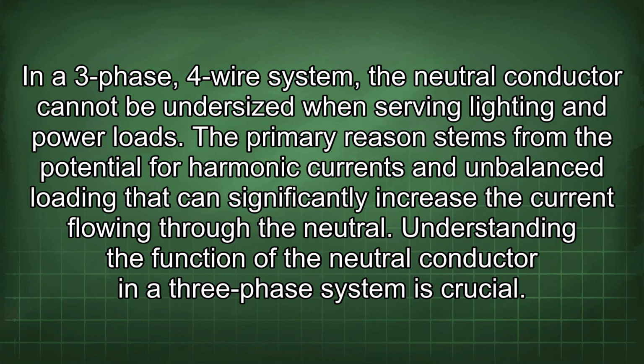In a three-phase, four-wire system, the neutral conductor cannot be undersized when serving lighting and power loads. The primary reason stems from the potential for harmonic currents and unbalanced loading that can significantly increase the current flowing through the neutral. Understanding the function of the neutral conductor in a three-phase system is crucial.